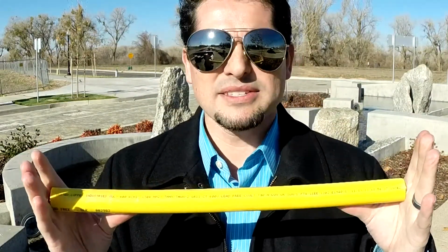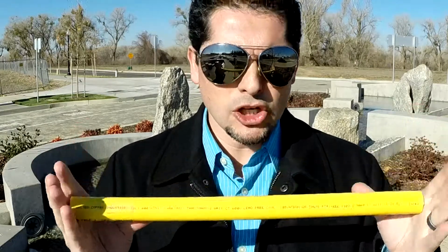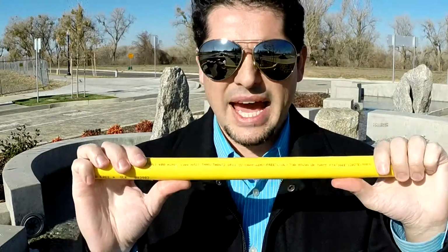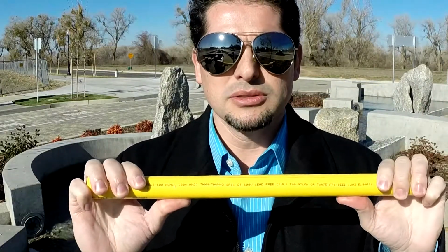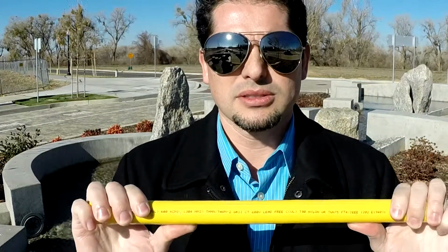Why don't they put the ampacity rating right on the outside of the cable? There's the volts right there. Why don't they just put the amps right next to the volts? Wouldn't that help people build things better and more safely so that they can check the amp rating right on there? So these fixed ampacities of this cable can be looked up in codes and standards. They have tables that show you this size cable has this much ampacity. And if you get the data sheet for this cable, which is available online, it will show you what the ampacity of the cable is.